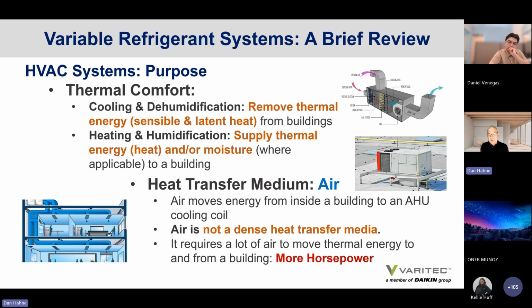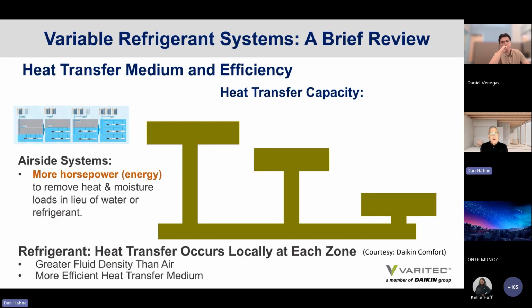Conventional HVAC systems, however, use air as a heat transfer medium. Air is a fluid and it has mass, so it can carry and convey energy. By injecting a large volume of air at relatively high velocity, 150 feet per minute at diffusers, a mixed air environment conceptually is created. So you have a plus or minus 2 degree temperature variation throughout the cubic volume of space. The problem is, if you use air as a heat transfer medium, it is not very dense. So you need a lot of air and consequently a lot of fan horsepower to move the building's energy.